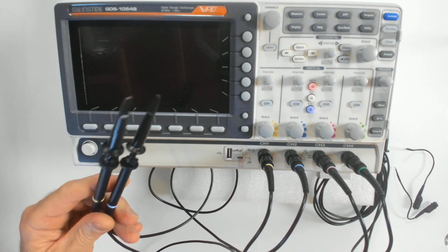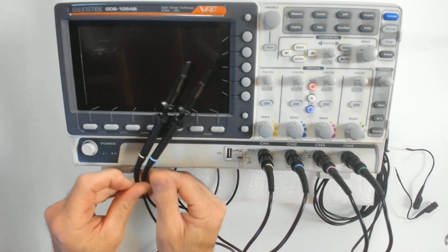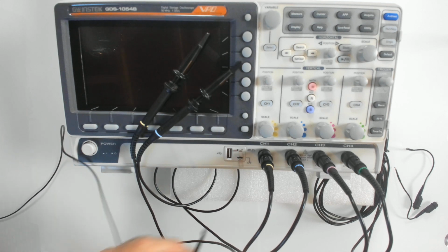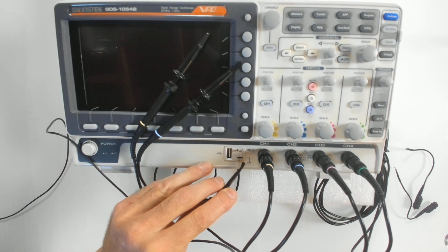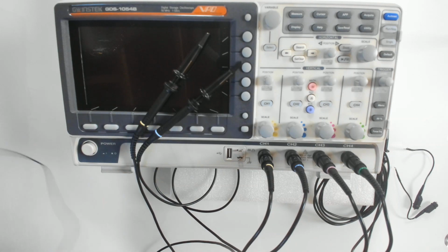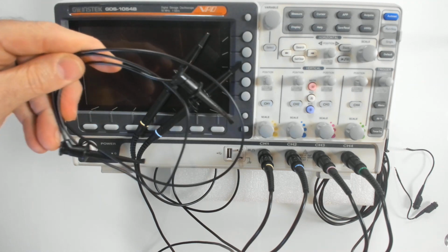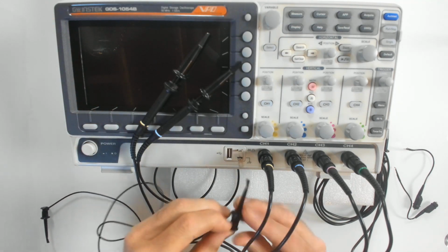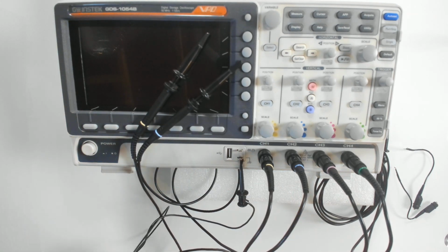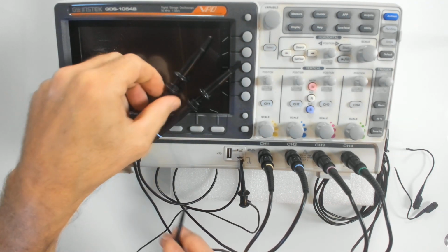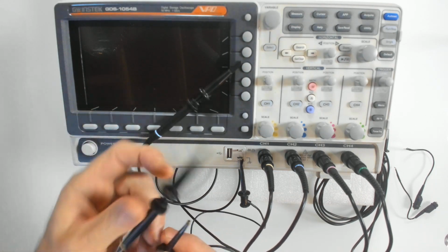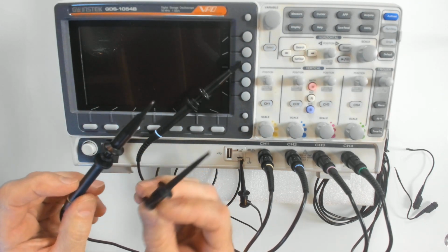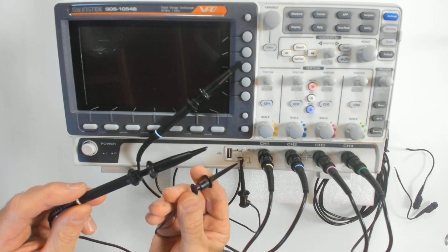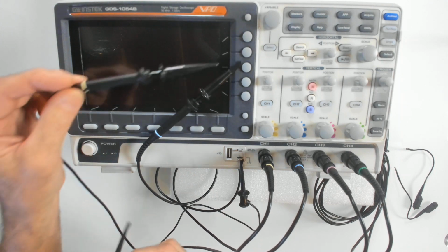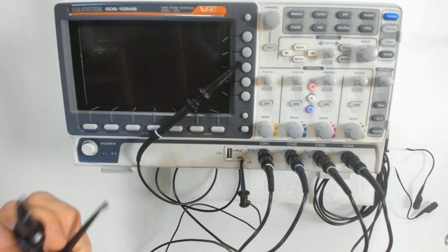So what I want to use is yet another connection point on the scope, which is also scope common, and that sits right here. You can see the little grounding symbol. So what I want us to do is use our little mini grabber to mini grabber test lead in your toolkit and just hook on to scope common right here. Okay, and that will be where you make the connection to your circuit common, and now voltages that you measure on channel 1, 2, and 3 will just be referenced to scope common right here and circuit common. So that's our common connection that we'll use. We won't use the ground clips. We don't need them at this point.